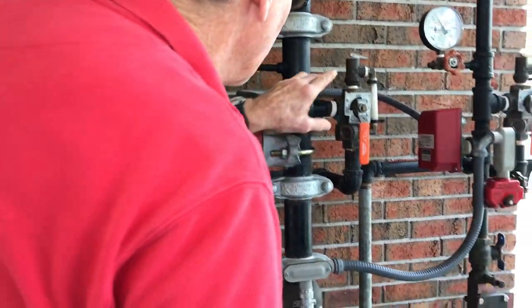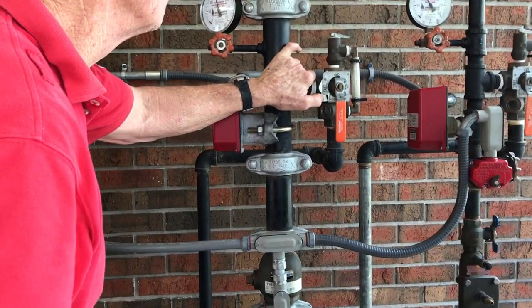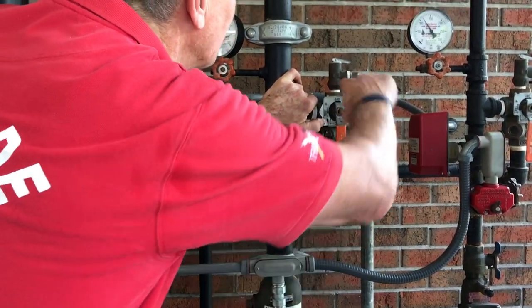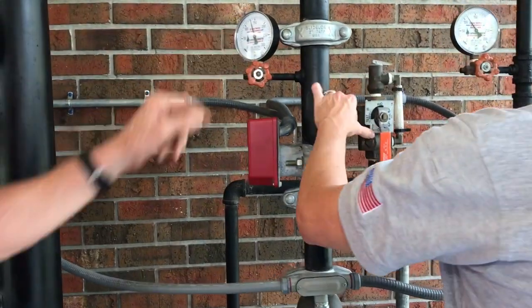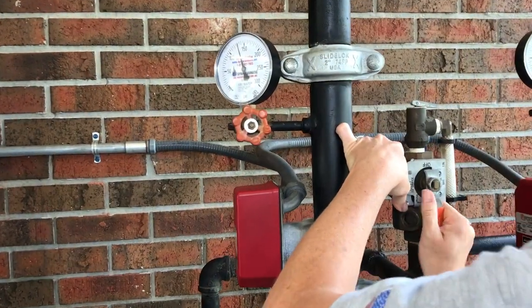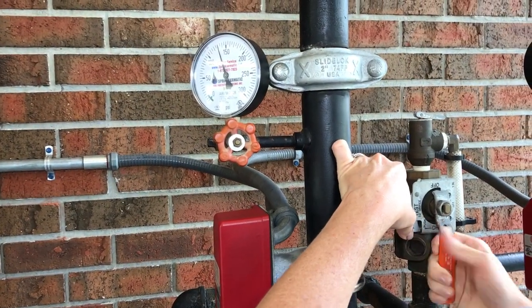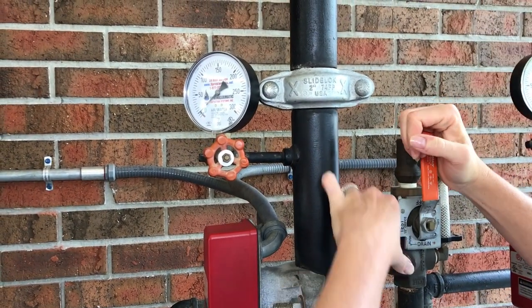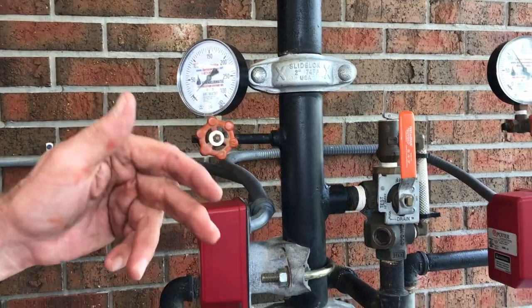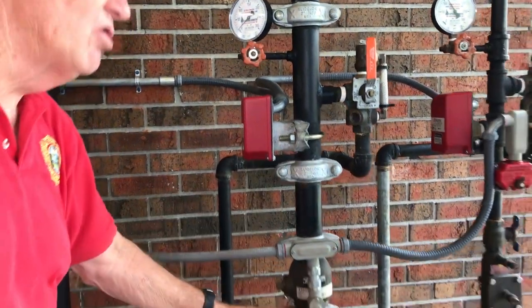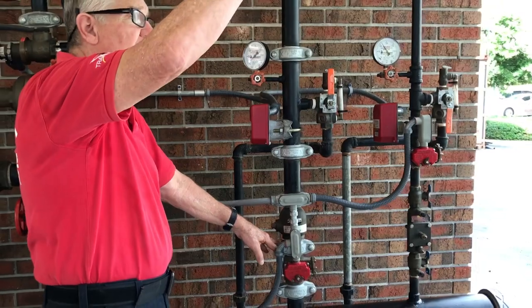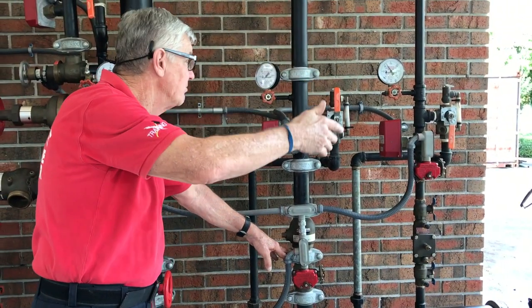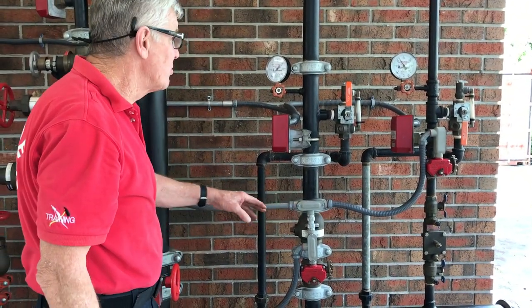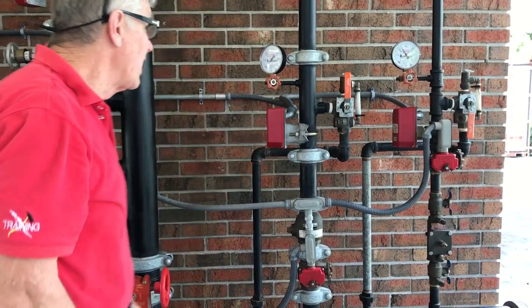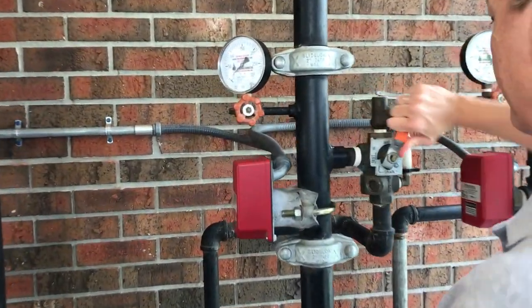Now here, since we've got it shut off, we're going to pull this lever and move this lever to drain. And you watch that pressure just drop. There you go. Okay. We've drained the water that was trapped between this closed valve and the open sprinkler head. They changed the sprinkler head. Okay. So now we're going to restore the system. We go ahead and we will close the drain.